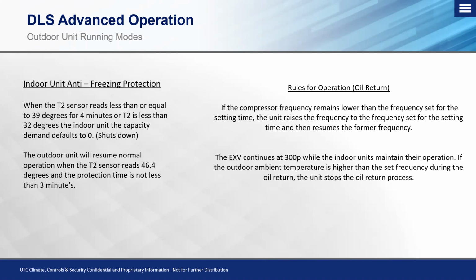So that EXV continues at that 300 pulse position while the indoor units maintain their operation. They will not shut down. If the outdoor ambient temperature is higher than the set frequency during the oil return, that unit stops the oil return process. Okay, and that's where that T4 sensor comes into play, the outdoor coil temp or outdoor ambient temperature sensor, on how we would stop an oil return process if it didn't run the 3 to 4 minute time period that we're trying to flush that oil back to the compressor.